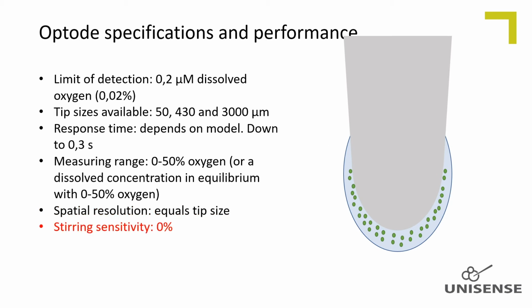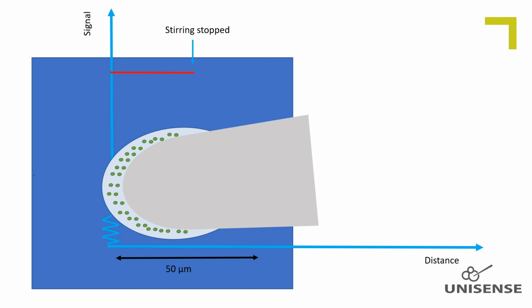An optode does not consume oxygen. Therefore, when measuring in liquid samples, and in contrast to Clark-type oxygen sensors, there is no diffusion boundary layer which can be affected by stirring. Thus, the optodes are insensitive to stirring. This is illustrated here, where stop and start of mixing a water sample does not affect the measurement.